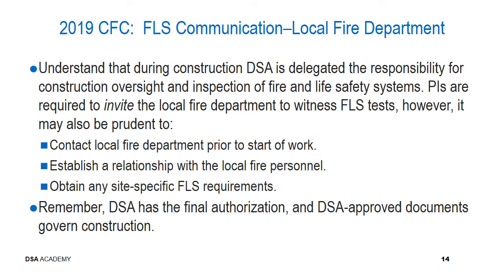Understanding that during construction, DSA is delegated the responsibility for construction oversight and inspection of fire and life safety systems. Project inspectors are required to invite the local fire department to witness all fire and life safety tests. However, it may also be prudent to contact the local fire department prior to start of work, establish a relationship with the local fire personnel, and obtain any site-specific fire and life safety requirements. Remember, DSA has the final authorization, and DSA-approved documents govern construction.